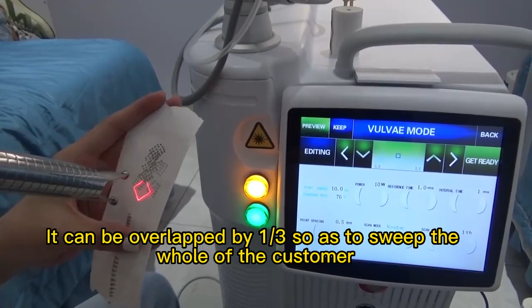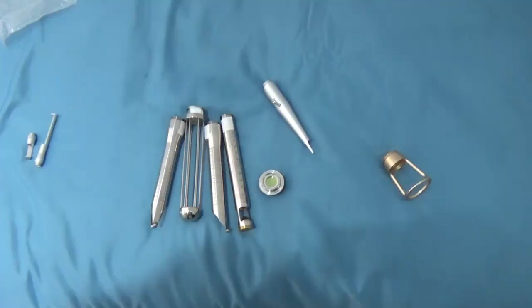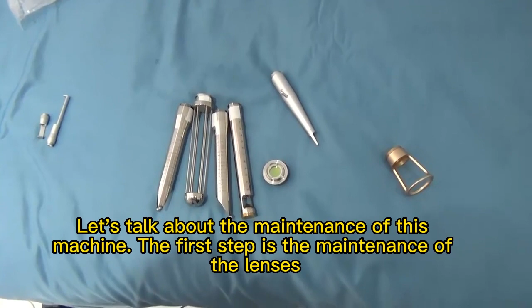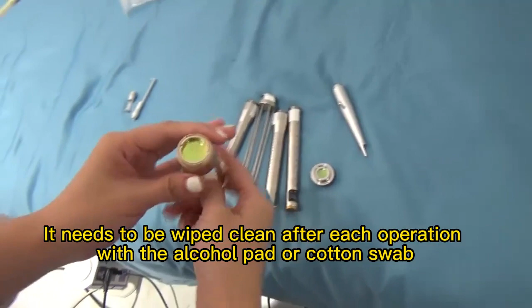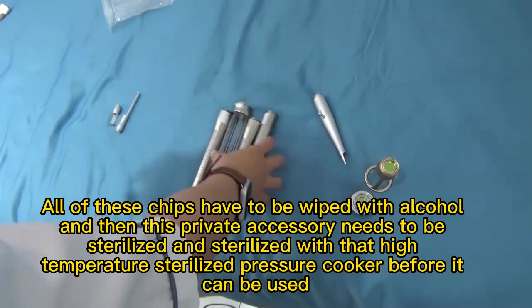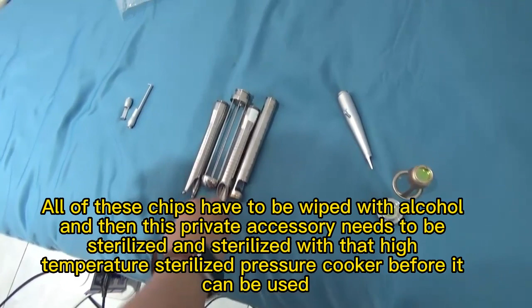Let's talk about the maintenance of this machine. The first step is the maintenance of the lenses. It needs to be wiped clean after each operation with an alcohol pad or cotton swab. All of these chips have to be wiped with alcohol, and then this private accessory needs to be sterilized with that high temperature sterilizing pressure cooker before it can be used. Then we can use alcohol to disinfect the other accessories.